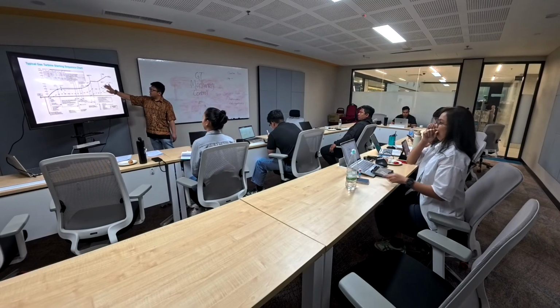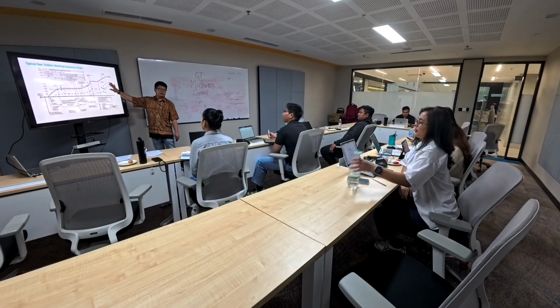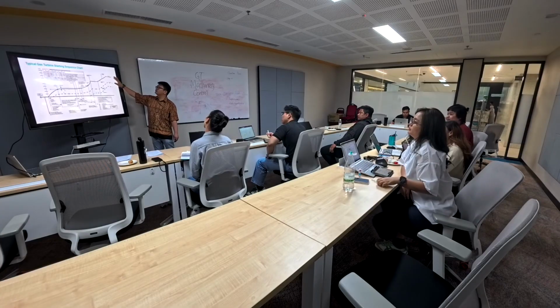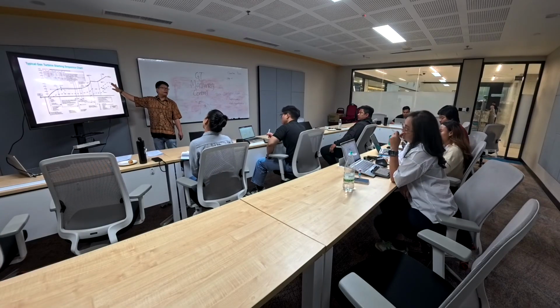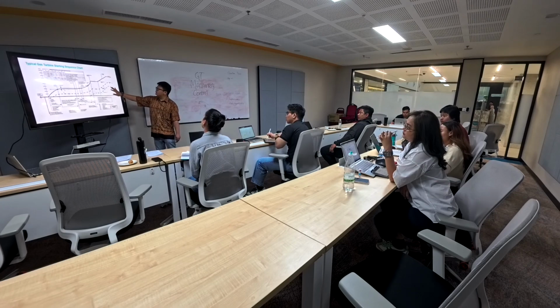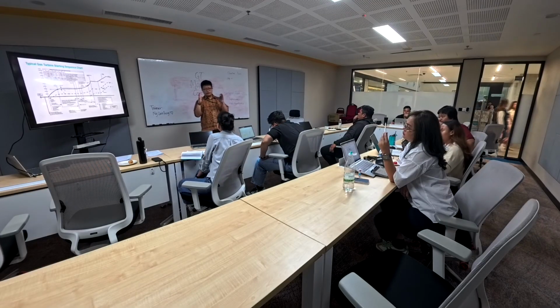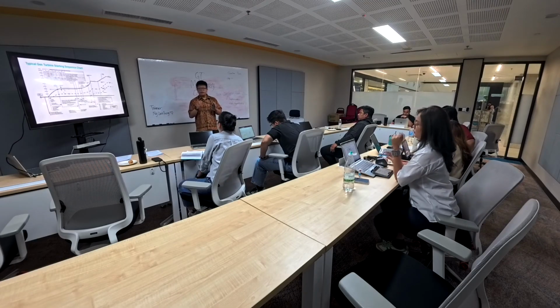The second dotted line is referring to the IP spool, which is just now we mentioned the twin shaft. This is the HP shaft. This is the LP shaft, IP. And then the third one is referring to the PT, which is aerodynamically coupled. Just now we mentioned twin shaft, in a twin shaft gas turbine, IP is referring to intermediate pressure.